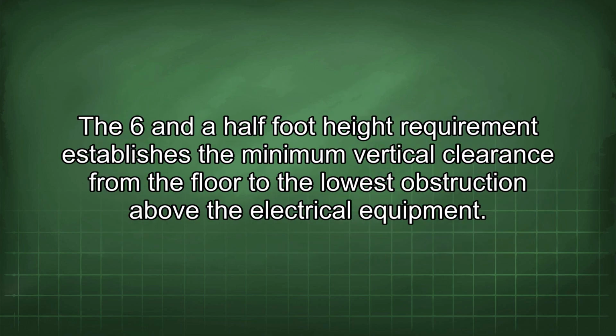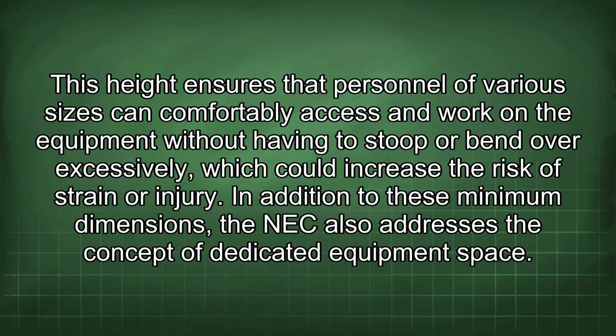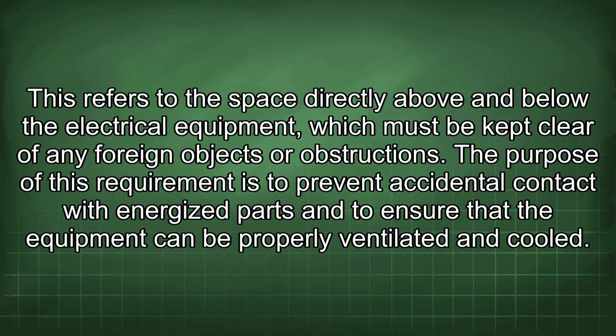The 6.5-foot height requirement establishes the minimum vertical clearance from the floor to the lowest obstruction above the electrical equipment. This height ensures that personnel of various sizes can comfortably access and work on the equipment without having to stoop or bend over excessively, which could increase the risk of strain or injury. In addition to these minimum dimensions, the NEC also addresses the concept of dedicated equipment space. This refers to the space directly above and below the electrical equipment, which must be kept clear of any foreign objects or obstructions. The purpose of this requirement is to prevent accidental contact with energized parts and to ensure that the equipment can be properly ventilated and cooled.